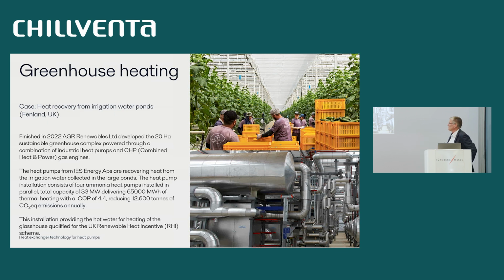It's situated quite far out in the countryside, so they are running a CHP plant for making the power, but they can reduce the carbon footprint here by having heat pumps, recovering heat from the discharge of the irrigation water, which they collect in ponds. And with this 33 megawatt heat pump that we have supplied condensers, evaporators, and products, we are delivering 65,000 megawatt hours of thermal heating. COP 4.4, reducing 12,600 tons of CO2 emissions annually. This could be higher if the power of the plant would be fossil-free electricity, of course. But this is where they are now, and that's got them a reward for the renewable heat incentive in the UK.